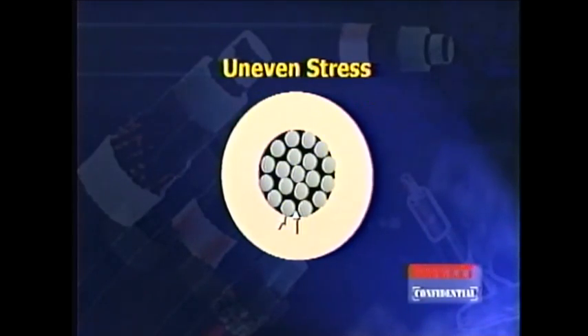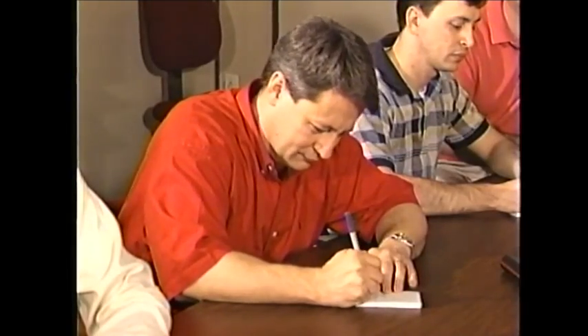One of the other reasons why you have a conductor shield at this interface is because where there's a high point in the conductor and a low point, you're going to have an asymmetrical distribution of your voltage stress within the cable insulating material. Again, this will be a problem.